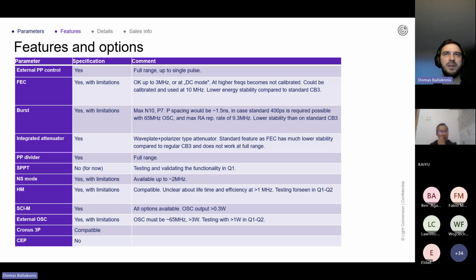But basically, we would be able to have the standard 400 picosecond burst spacing, but in that case, we will not achieve 10 megahertz of maximum frequency, but up to 9 megahertz, because we need to make a standard oscillator with a standard frequency of 65 megahertz. I already mentioned that the integrated optical attenuator is a standard option. Also, the pulse divider function is available at the full range in any division of the frequency.